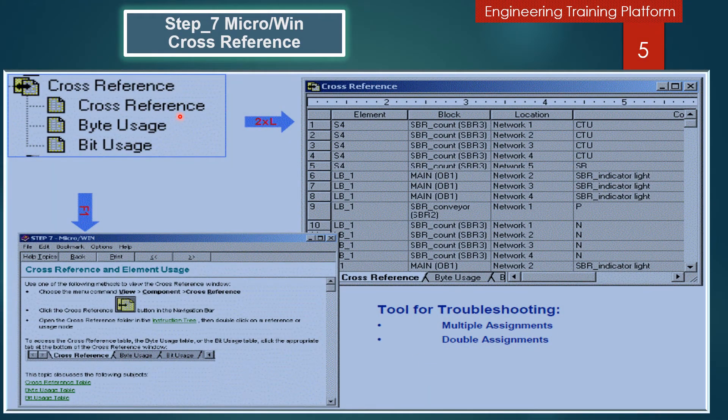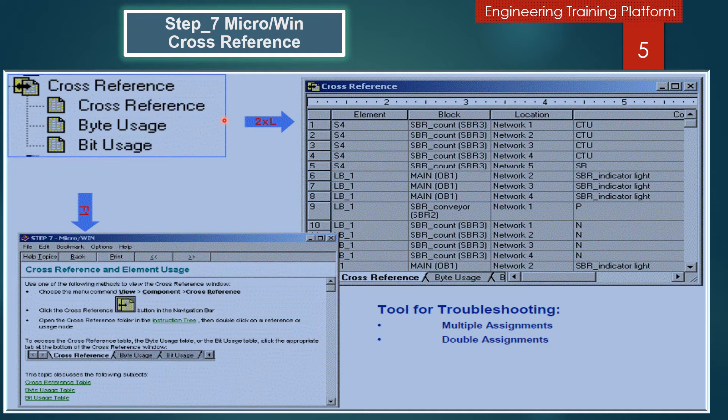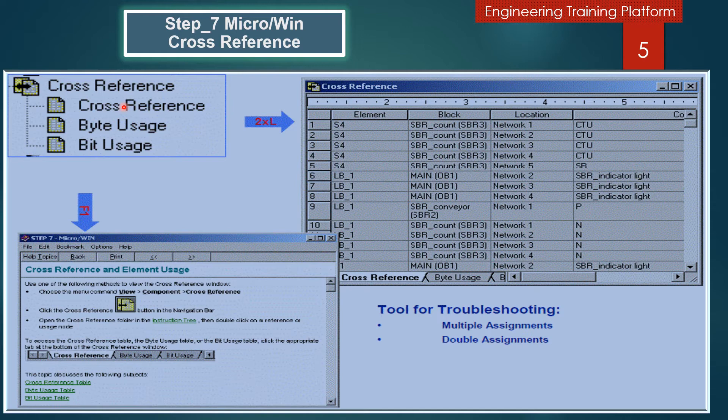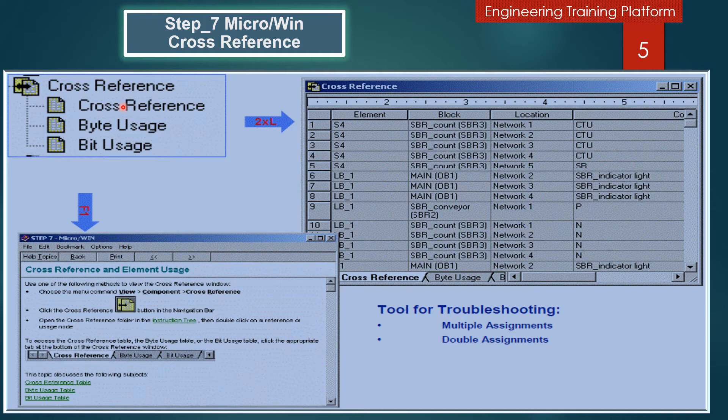In this slide we discuss the Cross Reference table, Byte Usage table, and Bit Usage table. Use the Cross Reference table when you want to know whether a symbolic name or memory assignment address is already in use in your program, and if so, where it is used. The Cross Reference list identifies all operand use in the program and identifies the POU network or line locations and instruction context of the operand each time it is used.